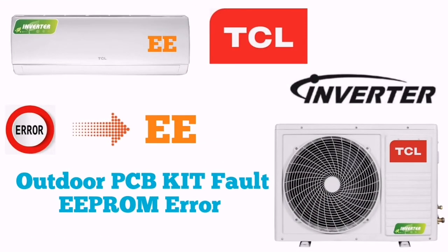When you see error EE, it means outdoor PCB kit faulty or EEPROM error. First of all, put the power off your unit and then check whether the indoor EEPROM installation is loose or improper. And if it is loose or improper, install it in the proper place and perfectly. And again, if you are getting the same error, then you have to go to the outdoor PCB and check the EEPROM in the outdoor PCB, because it has been built in and installed by the company itself.